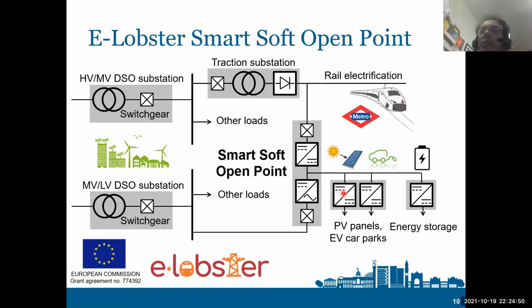A critical element to achieve this is energy storage, because direct feeding of the rail electrification may not be the best option, as that would only increase the transmission distance. Instead, we can inject into the public grid only the braking energy from regenerative braking of the train. All the energy normally not recovered within the rail network is sent through the smart soft open point to this network, increasing efficiency by increasing the amount of energy recuperated.